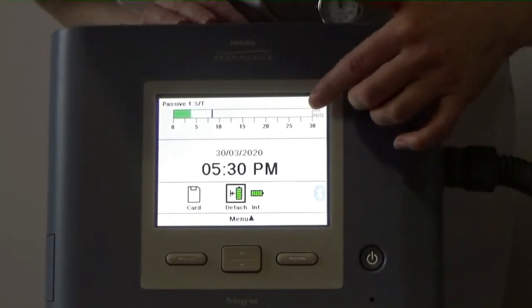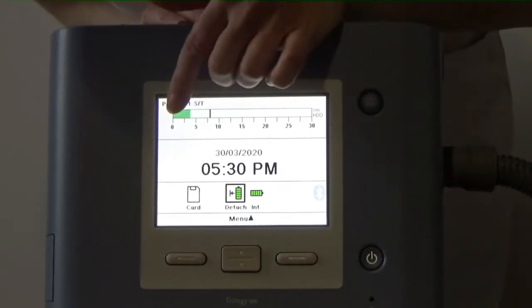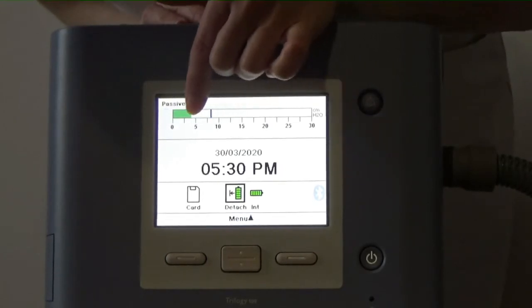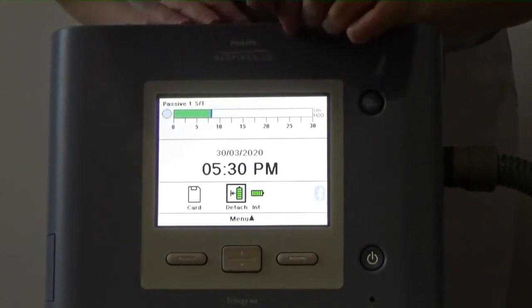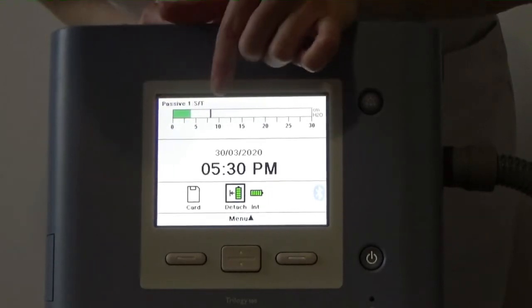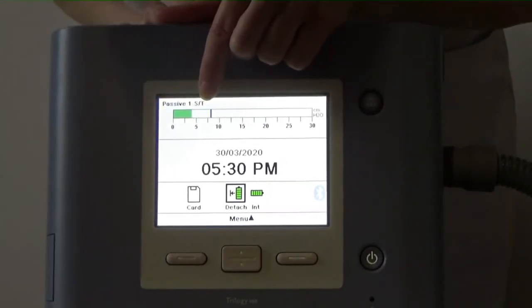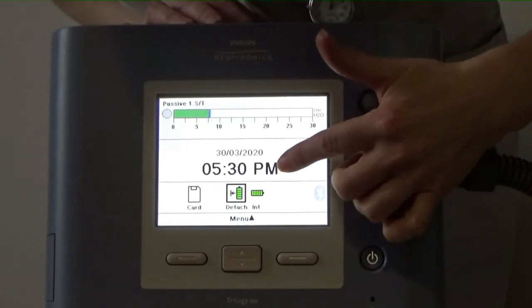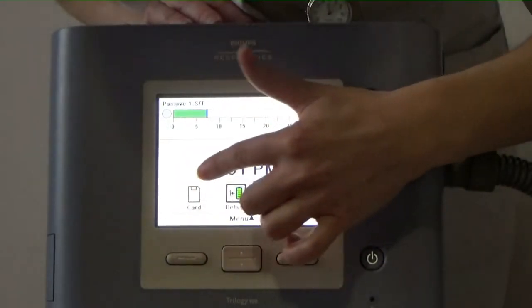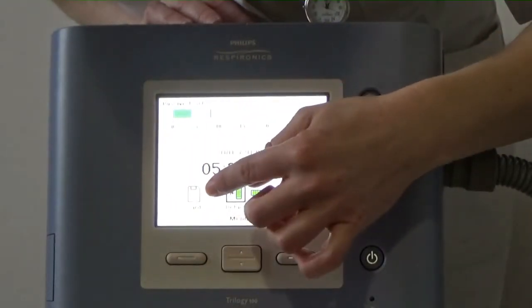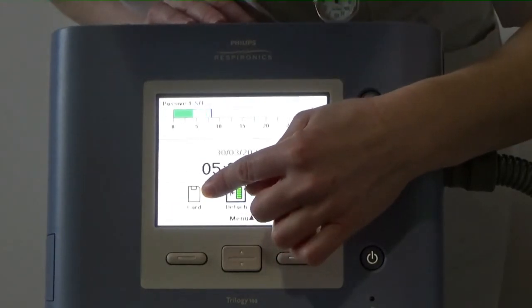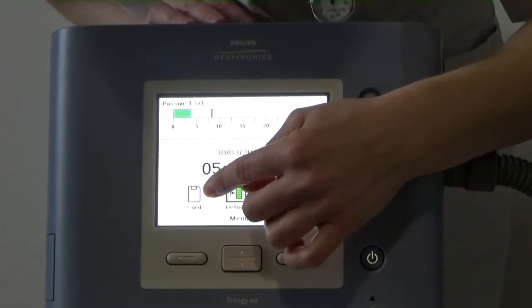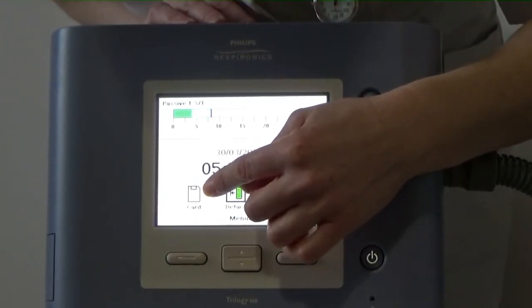You'll notice that as soon as you switch on the device, it starts to ventilate. On the screen, you can see at the top here a pressure bar. The pressure bar moves up and down as it provides pressure with the patient's breathing. In the top left-hand corner, it tells you which mode of ventilation we're in. Next, we can see the date and the time. In the bottom left-hand corner, we can see a picture of the SD card. If this has a cross through it, it means that there is an error with the SD card, in which case we would ask you to remove the SD card and we would send you a replacement. The ventilator will continue to work without the SD card in place, it just won't be recording any data.